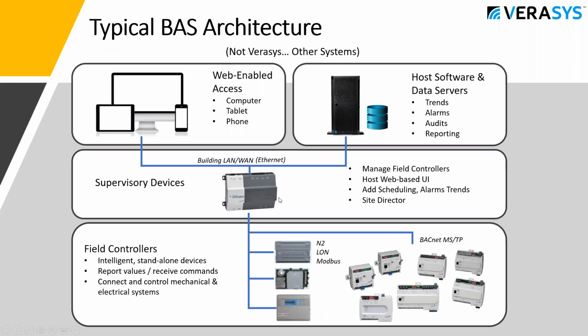This is essentially the site director for all of the equipment that lives downstream of it. These engines are powerful and may talk multiple protocols, but they require a lot of setup and addressing to manage all the points on the field devices. Mapping and addressing needs to be done before you can create your schedules, alarming, and trends in this JACE or supervisor controller. So it can be expensive, time consuming, and requires somebody with quite a bit of training. In addition to the labor, licensing for these controllers can be very expensive and may not be necessary for simple building integrations.